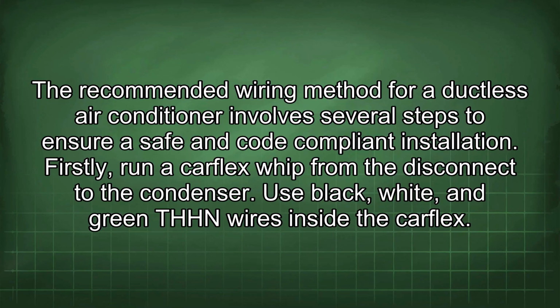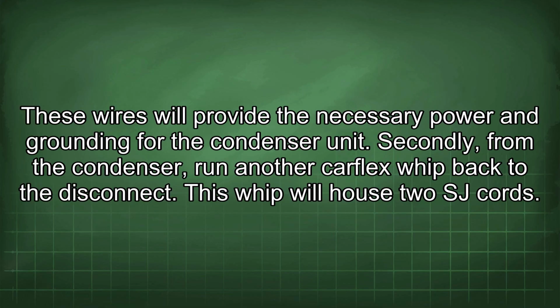The recommended wiring method for a ductless air conditioner involves several steps to ensure a safe and code-compliant installation. Firstly, run a carflex whip from the disconnect to the condenser. Use black, white, and green THHN wires inside the carflex. These wires will provide the necessary power and grounding for the condenser unit.